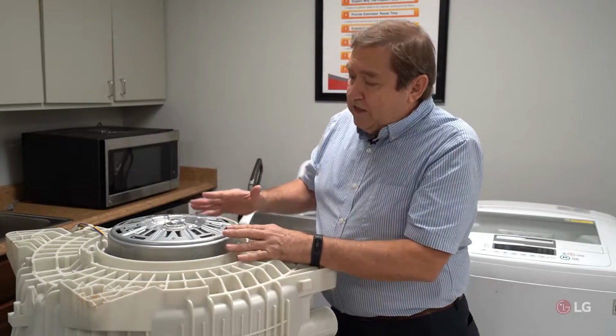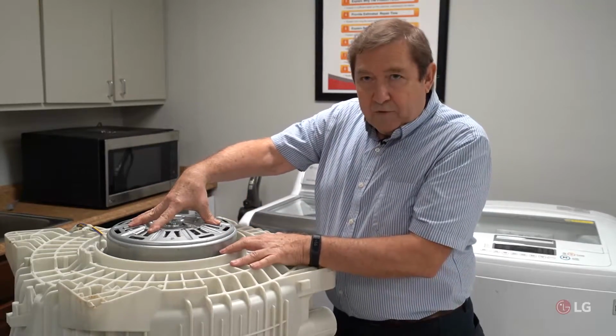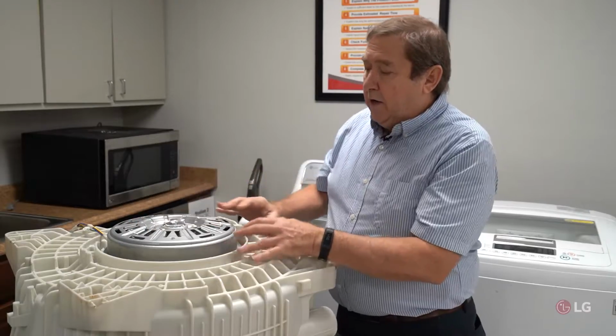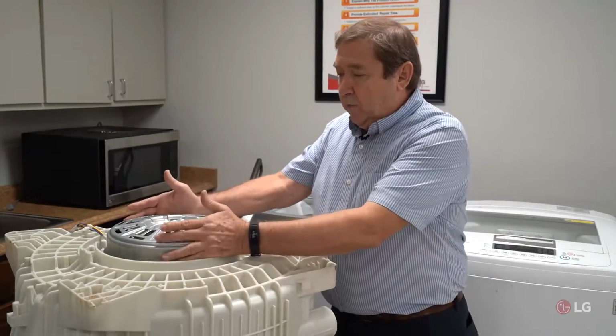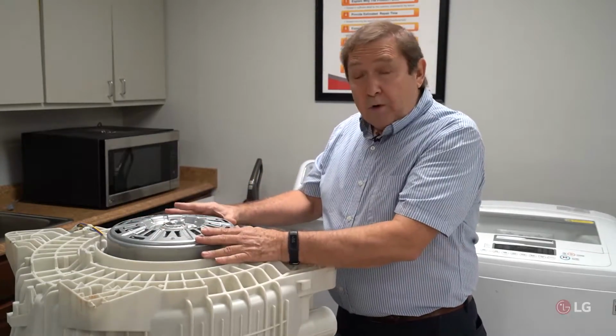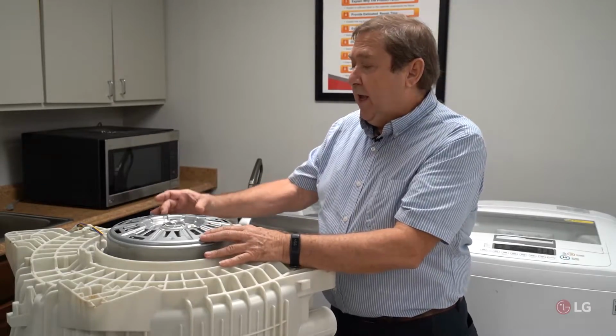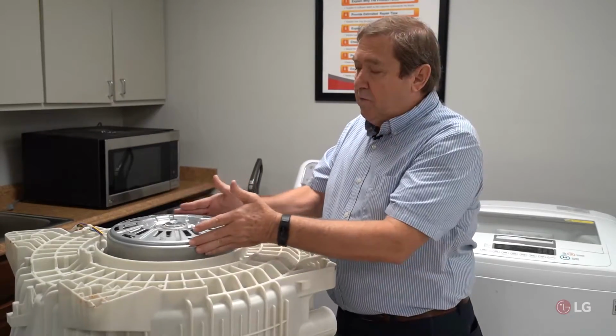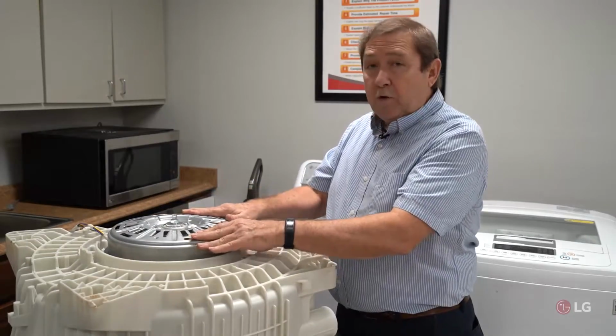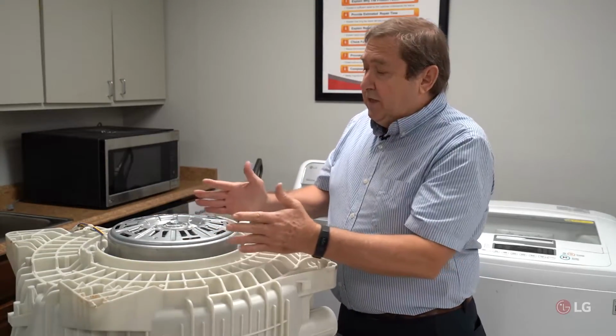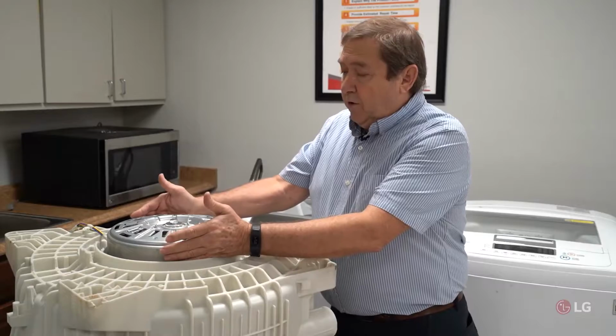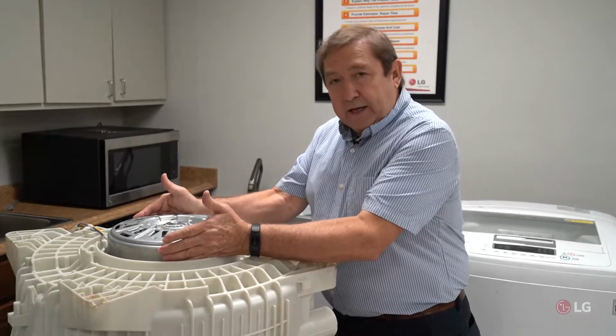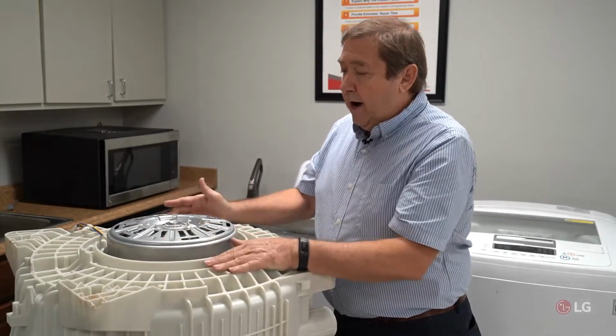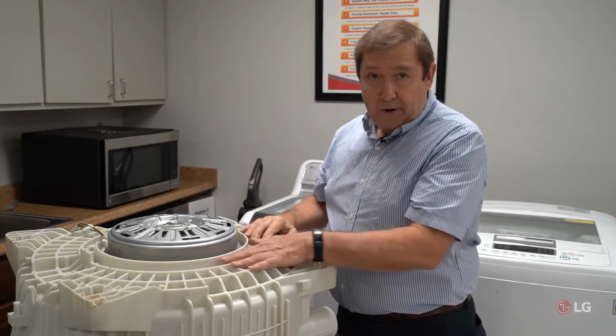Lock rotor basically means this rotor is being prevented from turning. It could be a problem with the stator, a problem with the rotor, or on some earlier models we had a device called a Hall sensor, which monitors the rotation of the rotor, and that could be defective. So basically the rotor is trying to rotate and it gets bound up, and that's what generates the LE error code.